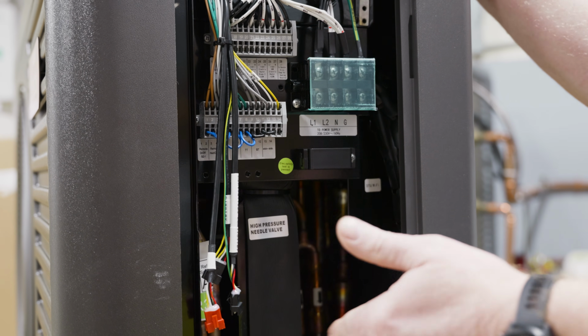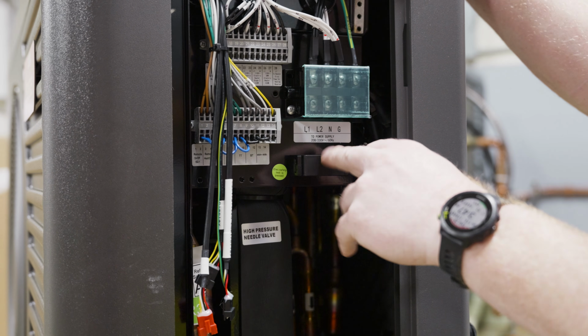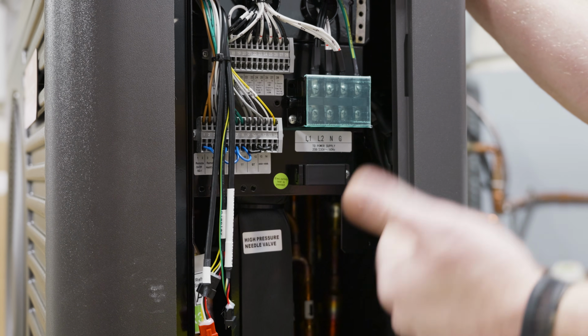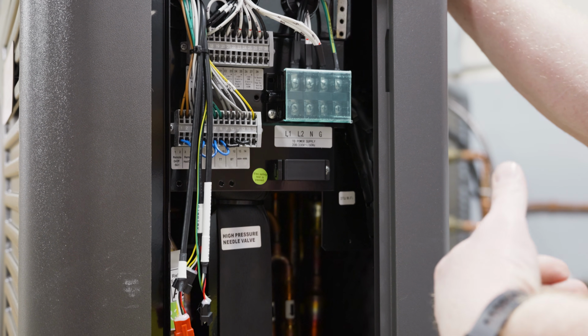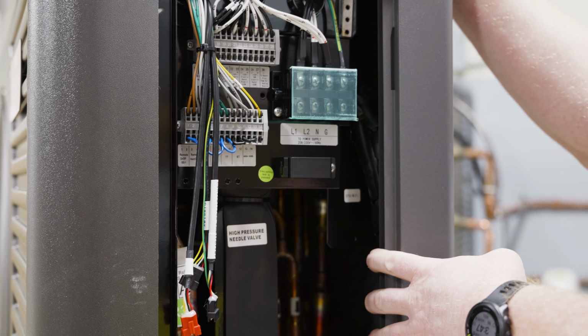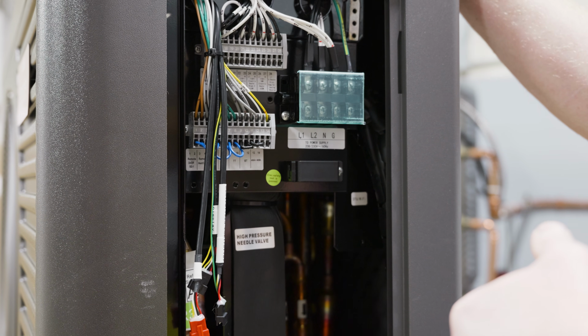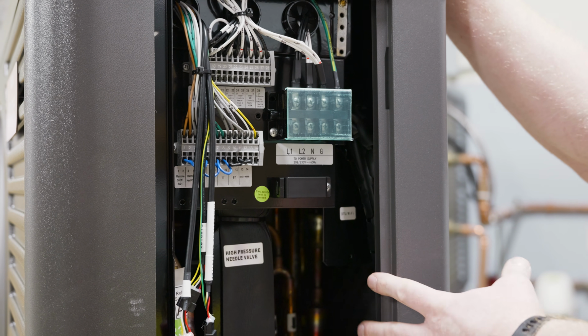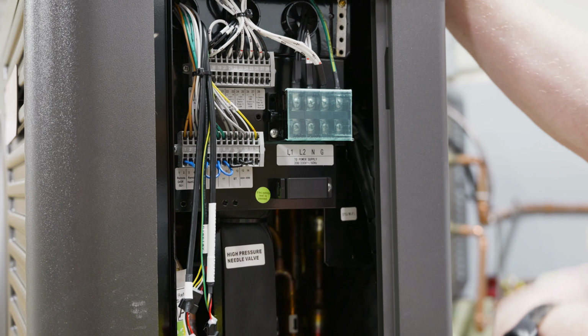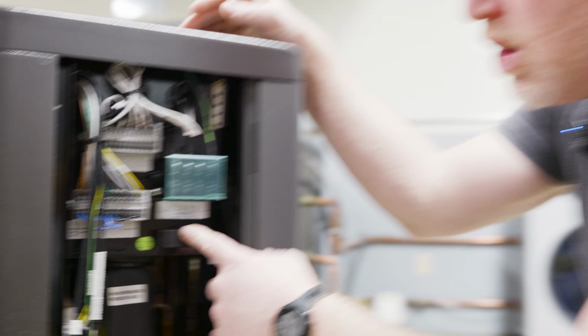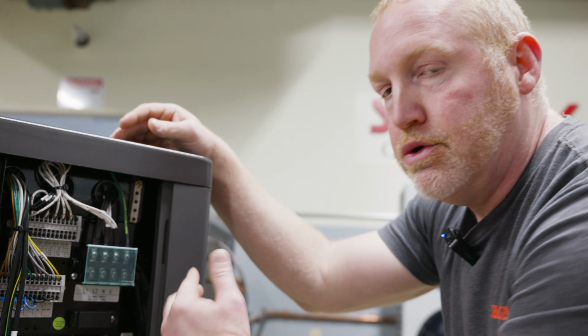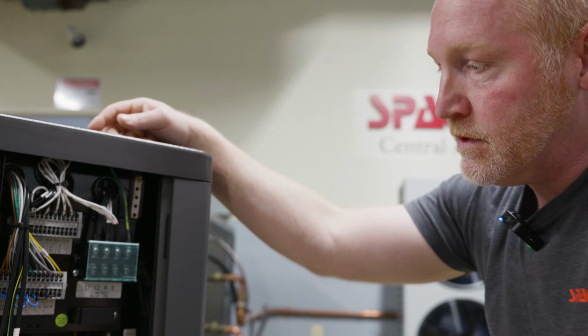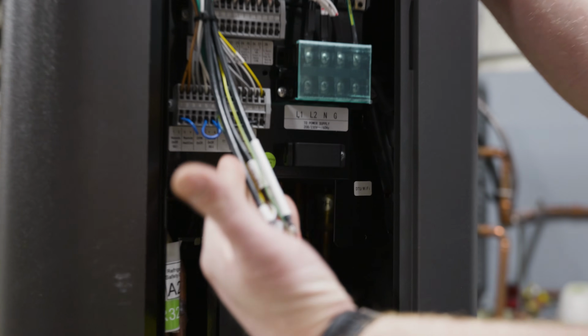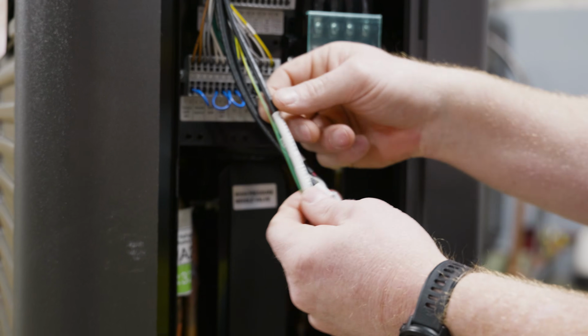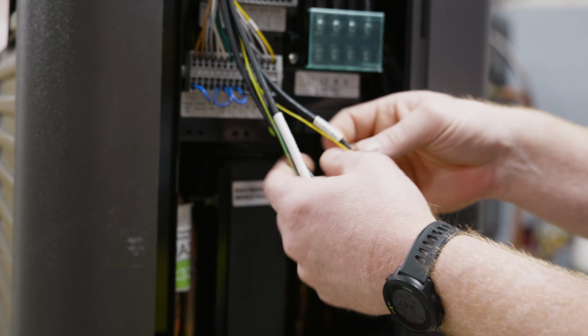One of the things that I'd like to bring attention to here is the need for that neutral and a ground. The circulator that moves the water or water glycol mixture from the heat pump outside to the buffer tank inside and then back again is controlled by the outside unit. So if we're running a 110 volt circulator, 1 leg of power and a neutral is required for proper operation. We move over here to our cables, easily marked on these white labels.